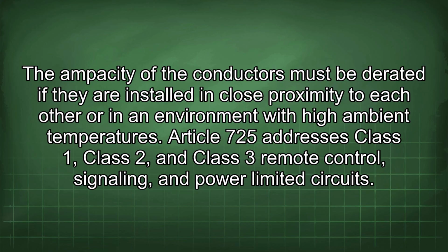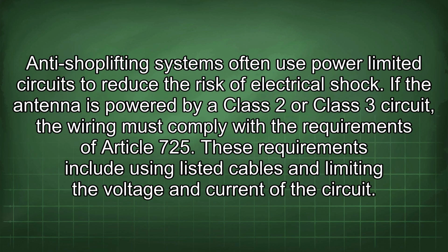Article 725 addresses Class 1, Class 2, and Class 3 remote control, signaling, and power-limited circuits. Anti-shoplifting systems often use power-limited circuits to reduce the risk of electrical shock. If the antenna is powered by a Class 2 or Class 3 circuit, the wiring must comply with the requirements of Article 725. These requirements include using listed cables and limiting the voltage and current of the circuit.